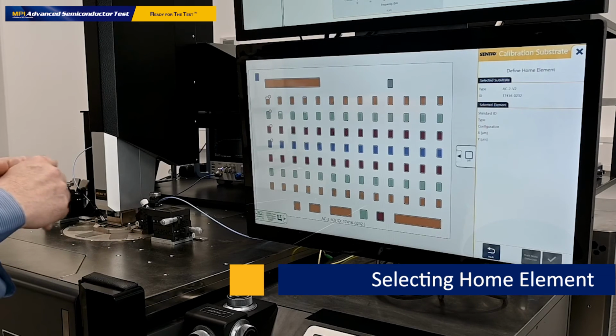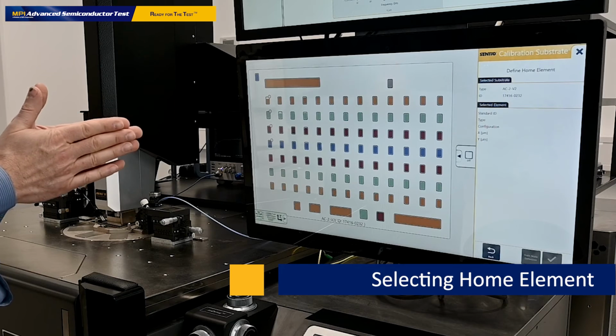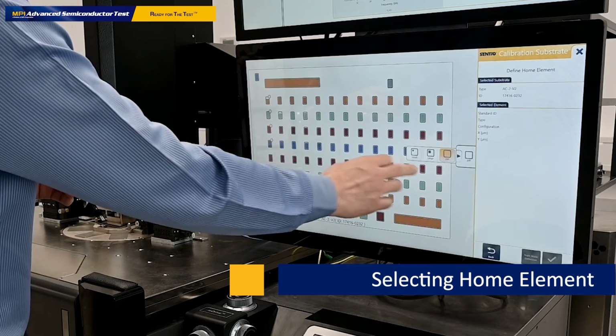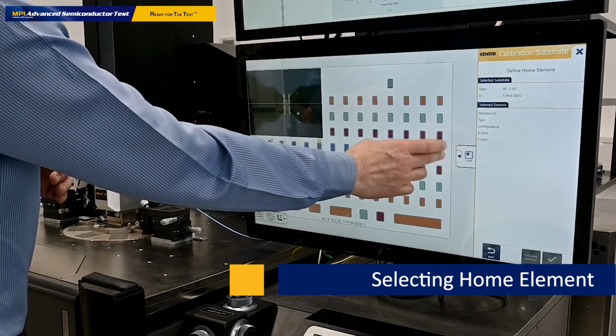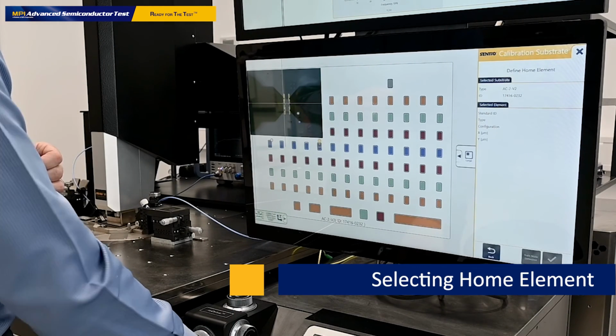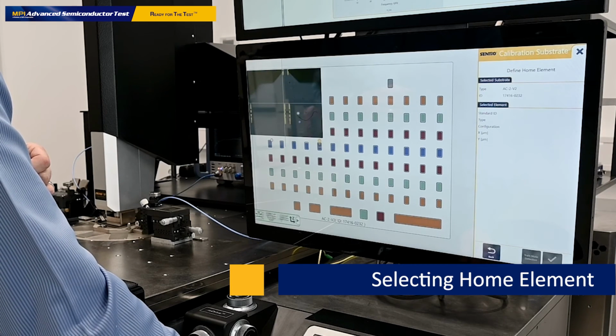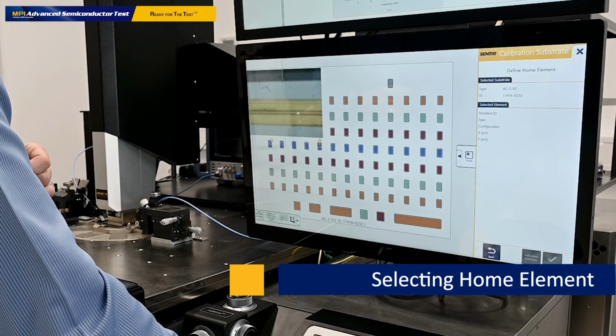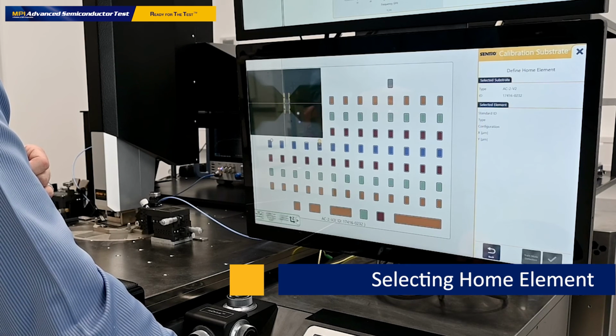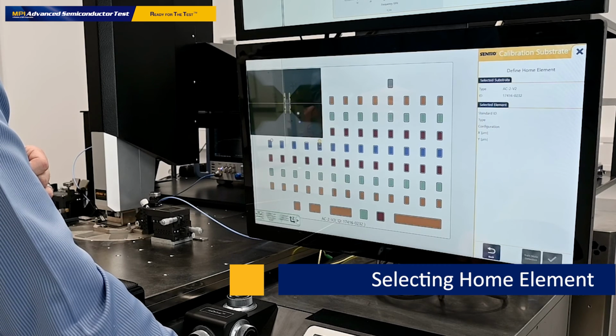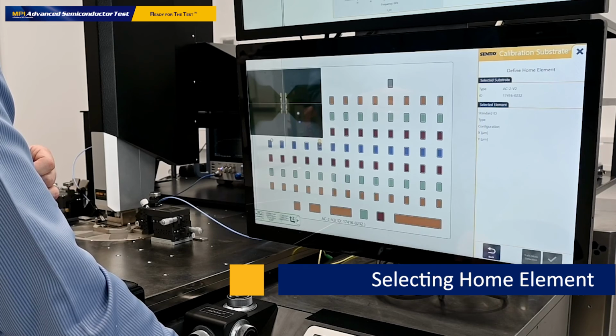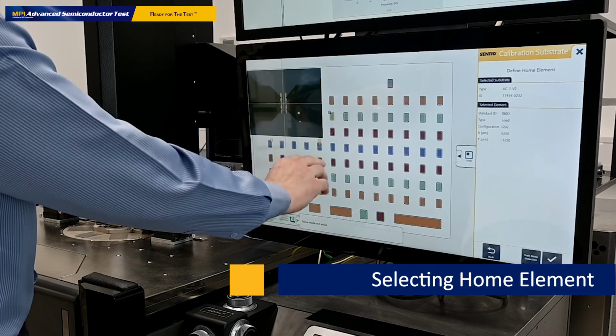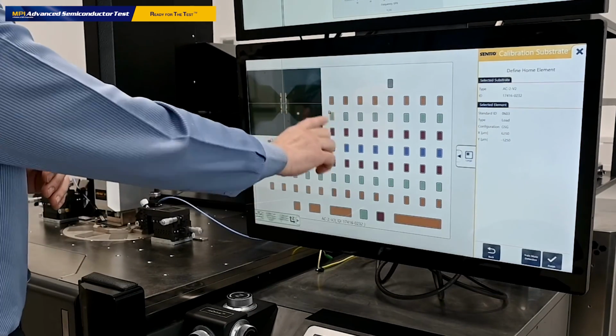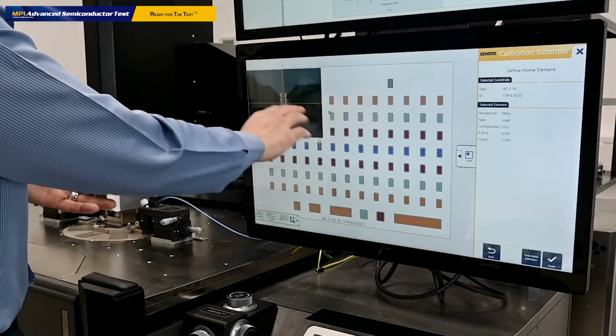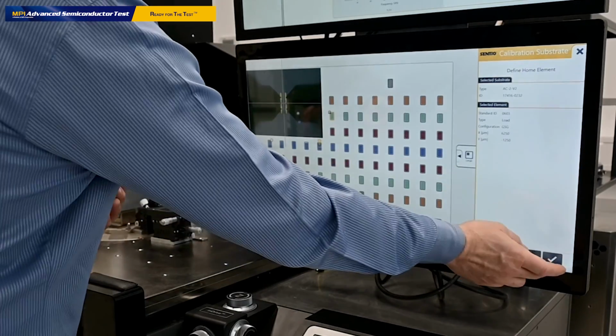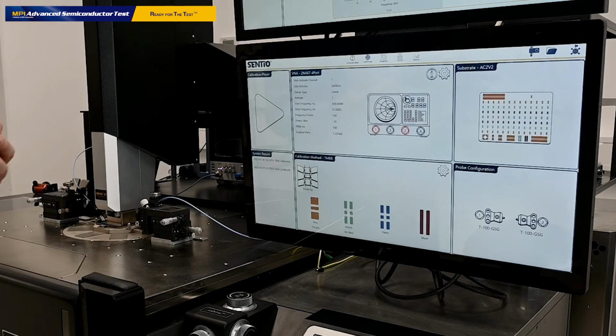We brought the probes into contact, and now the last step for us is to select our home element, which is currently, we don't know where we are, right? So let us enable the view of the microscope and check where we are currently located. Which standard is it? We are in the middle, so let us count the number of the standards. So this is 1. So we should be here. So this is the one element which we use as our home element, and we have a little bit of home mark which shows us this element is selected now as our local home. And by doing this, we finish the procedure, and now we are able to use the calibration standards for the entire calibration process.